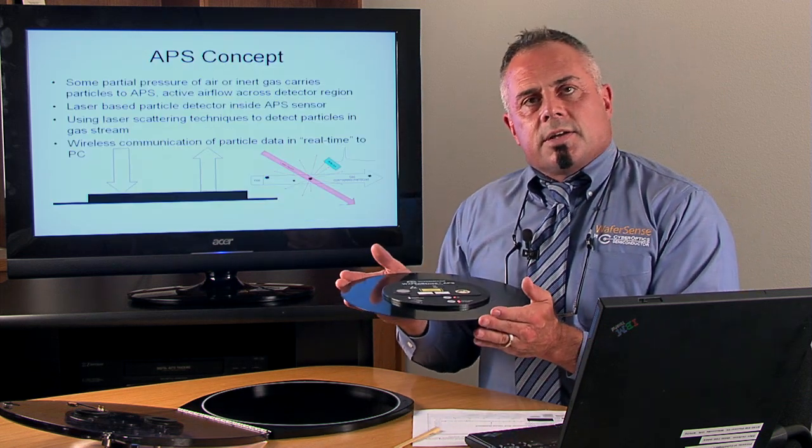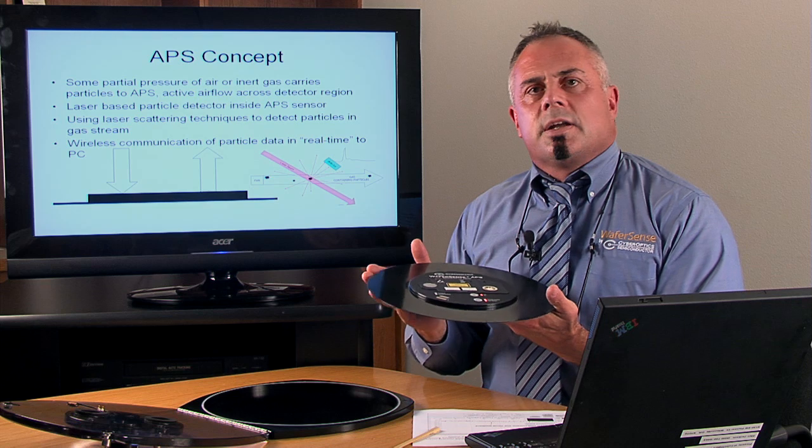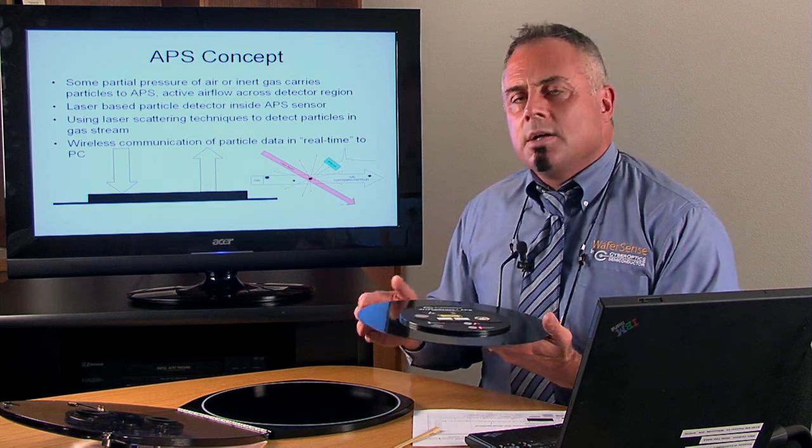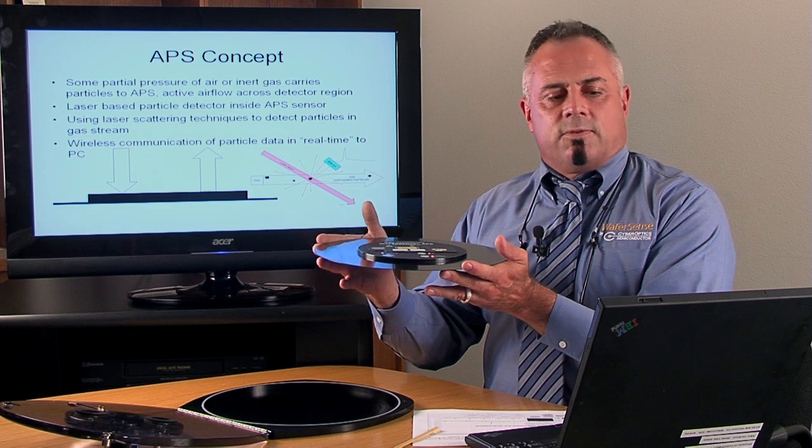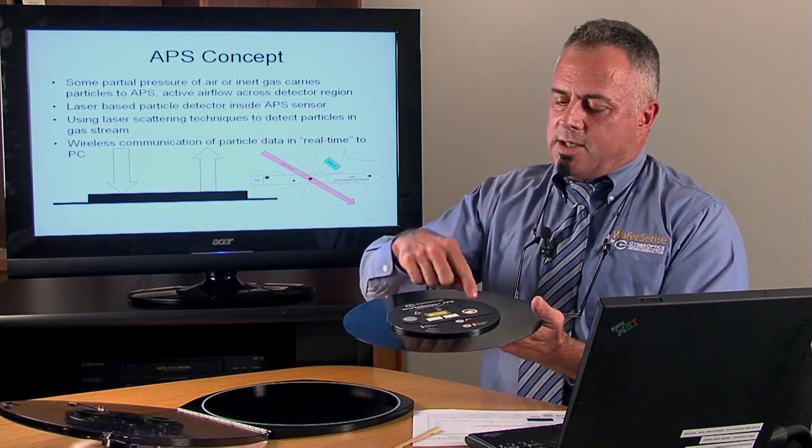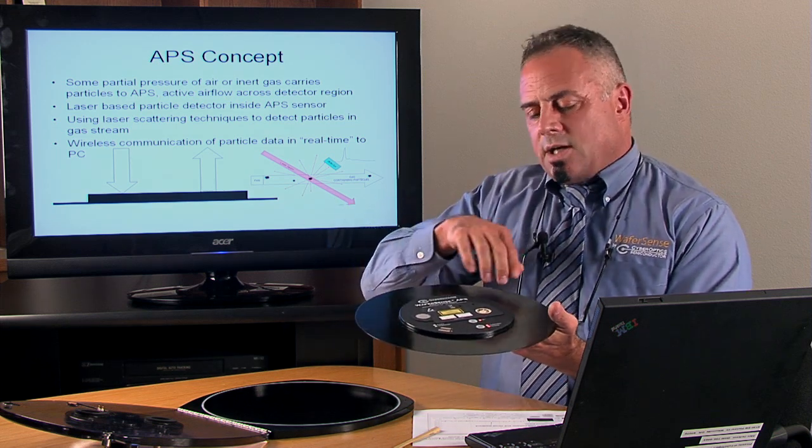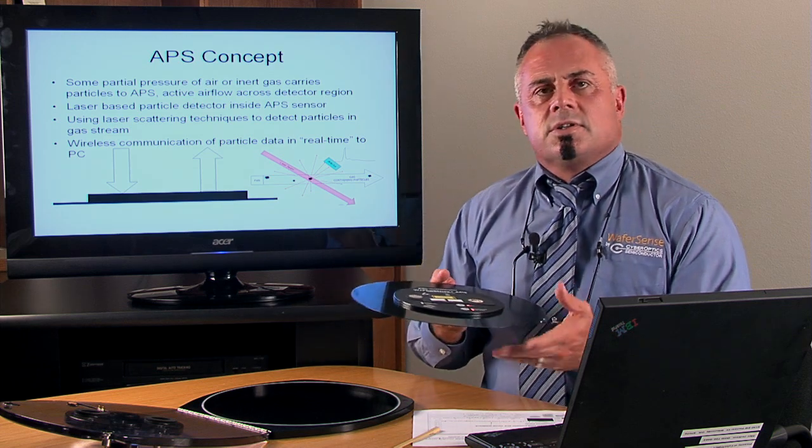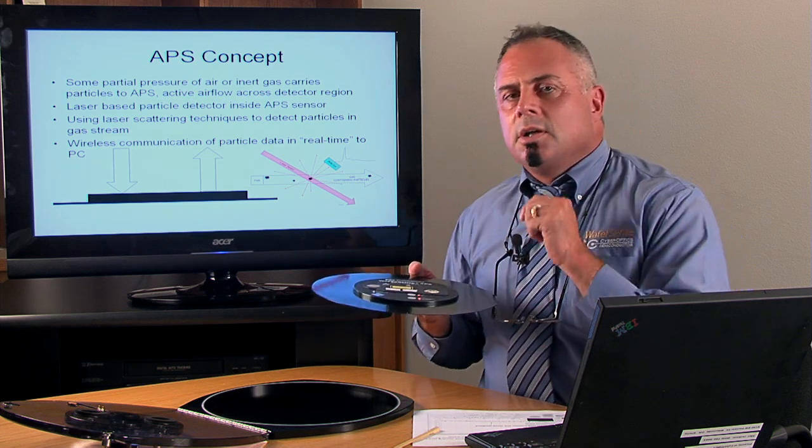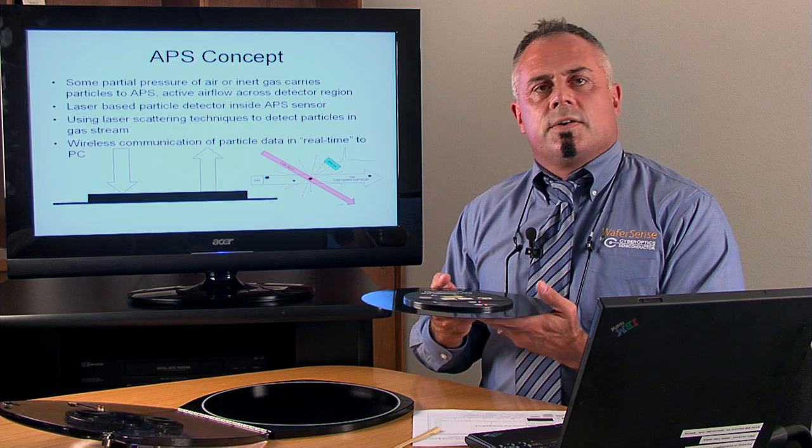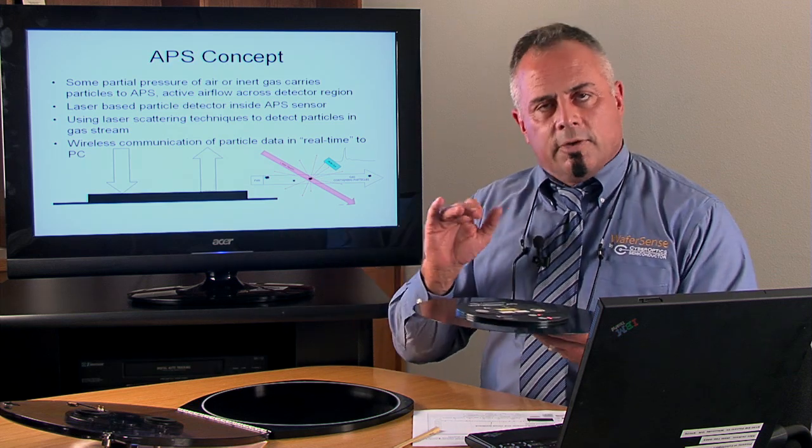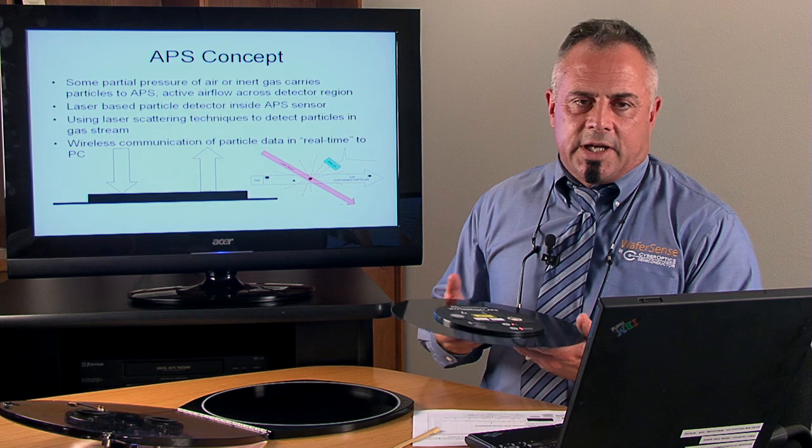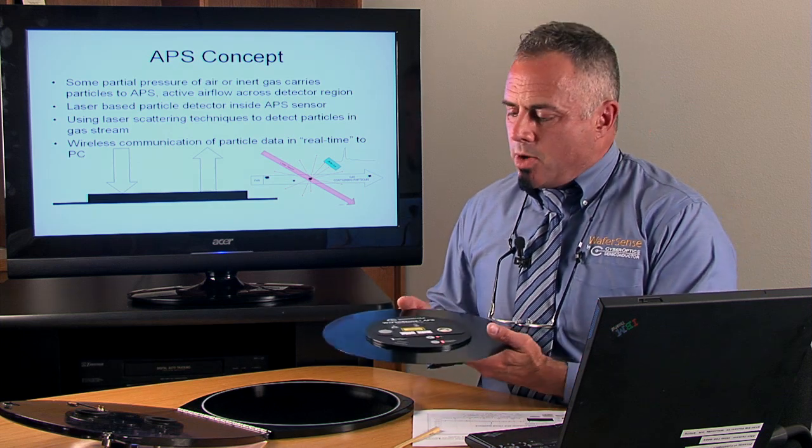The way APS works is it's considered a benchtop or a handheld atmospheric particle counter shrunken down into the wafer format. It's got a fan, it's got lasers and detectors inside, it blows the air through, it counts the particles and uses Bluetooth wireless communication to communicate out the particle data from deep within the tool and sends it to your application software and records it for monitoring.